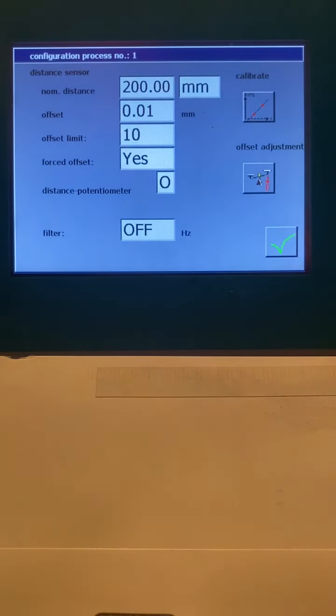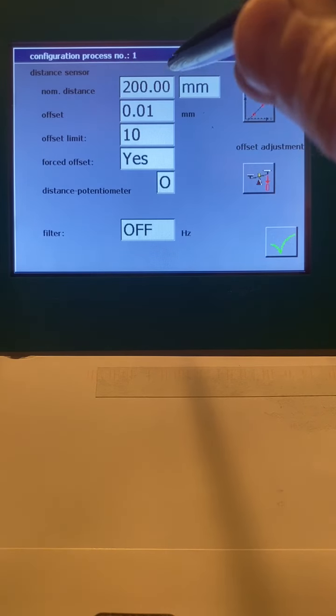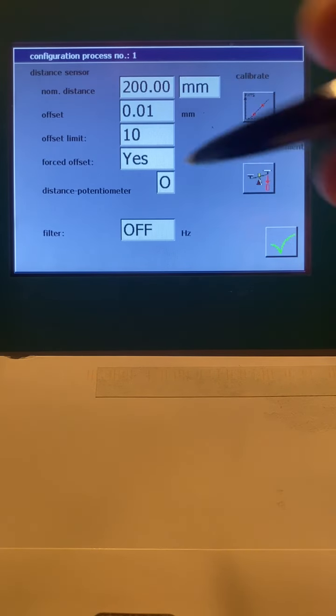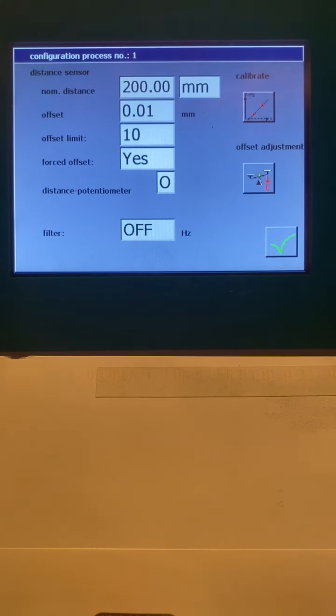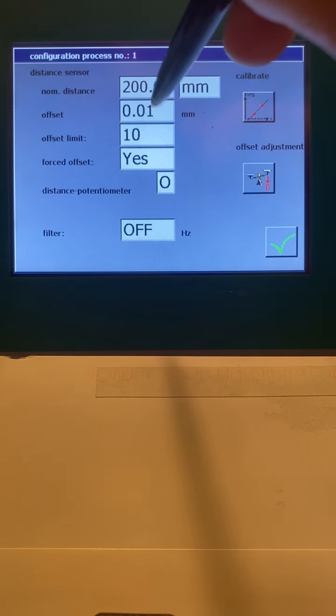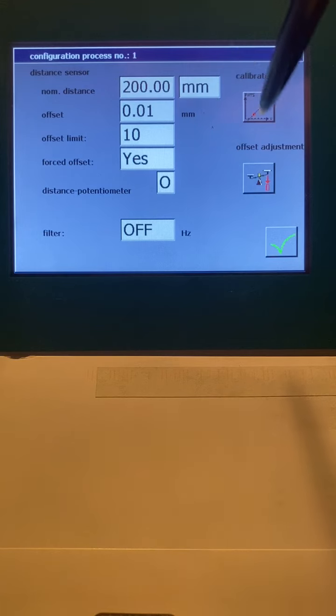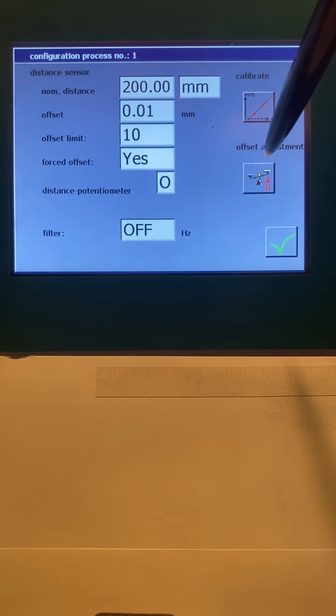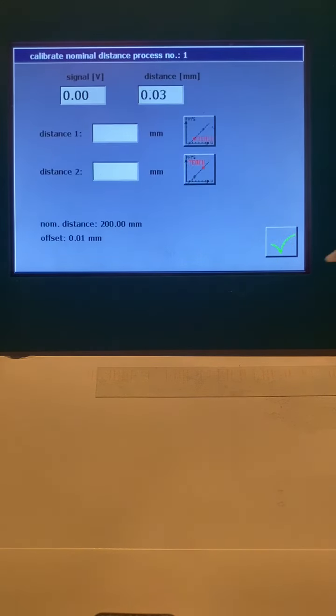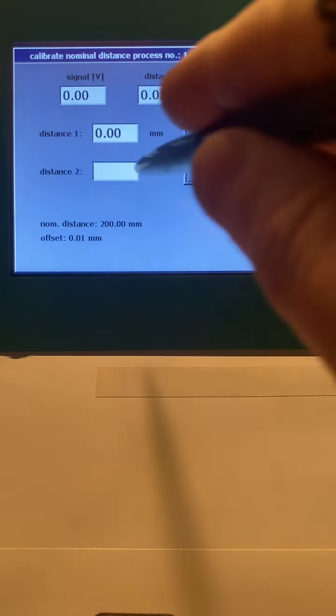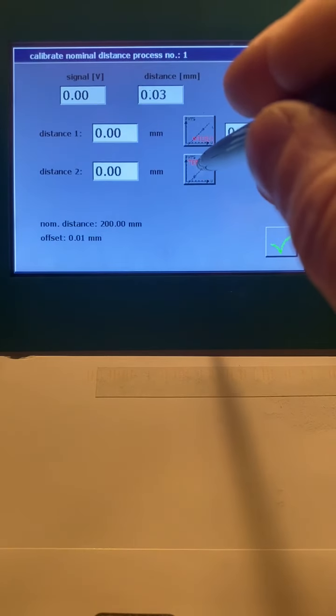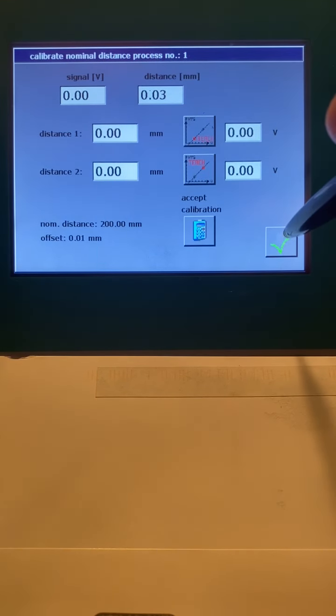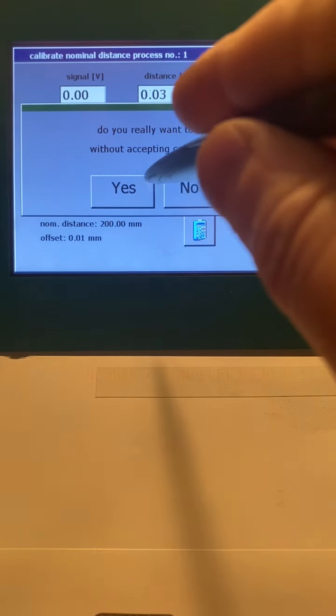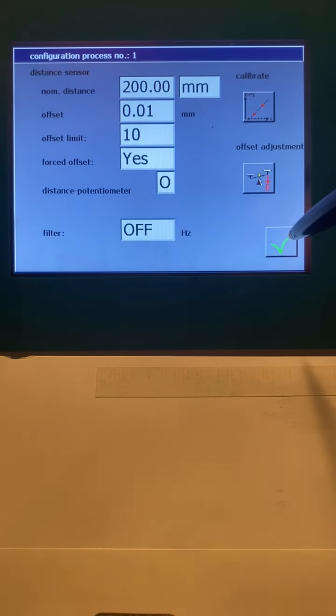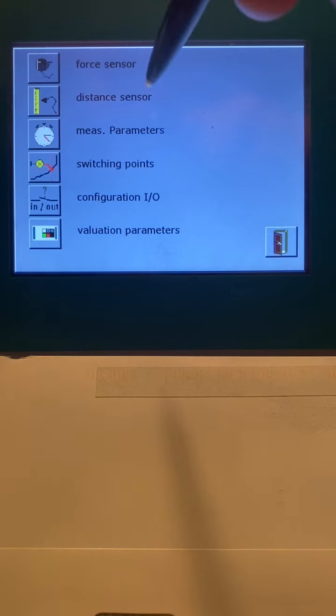I can also go to my distance sensor and do the same thing. It's a 200 millimeter total stroke. My offset is 10, which means that 0 happens at this small piece. Here's my offset adjustment, which is a 0, and I can do a 2-point calibration. Same thing. 0 is 0, and 0 is 0. 0 volts, okay? That's what that does. So really, what I've got here is the ability to set up my distance sensors.